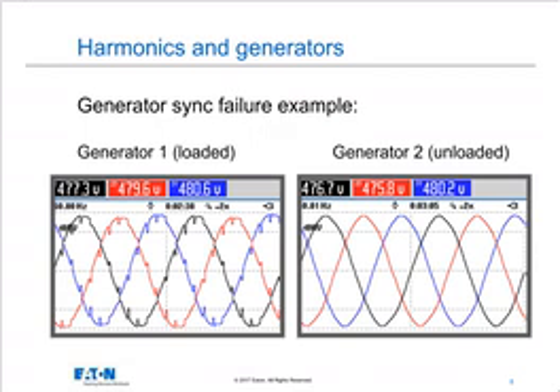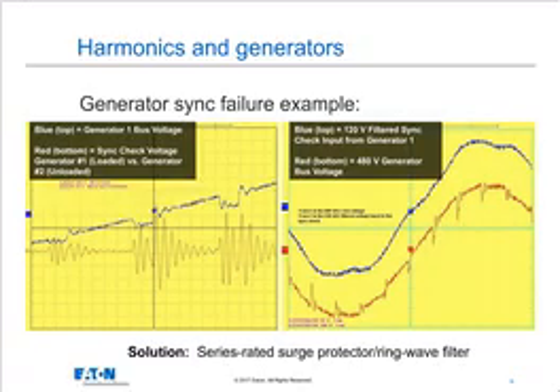Now what happened in this case was they had paralleling switchgear, so they had an unloaded generator that was trying to parallel with the loaded generator, and the loaded generator's distortion was so significant that every one of those notches created a little impulse on the synchronizing relay. So when they had a sync check voltage across those notches, it looked like there was something wrong and they couldn't parallel the two generators. So now you have to run all of your load on one generator instead of sharing the load between two.